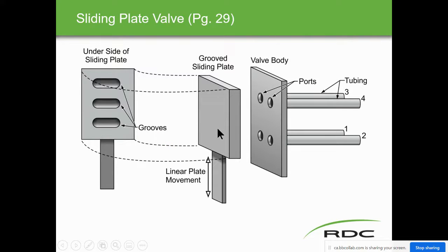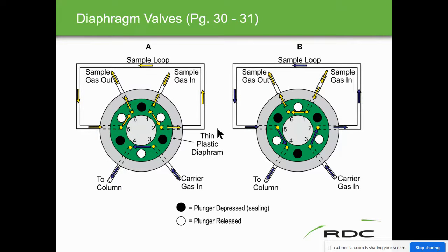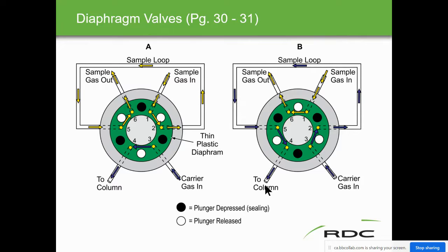Alternative valve types include a sliding plate valve and a diaphragm valve. With the diaphragm valve in position A, sample comes in and goes out; carrier gas always flows. Switching to position B: sample goes to vent while the carrier gas takes all the sample trapped in the sample loop and pushes it to the column. The diaphragm — plunger depressed seals it, plunger released opens it — controls the amount of sample injected by filling the sample loop and pushing it to the column.